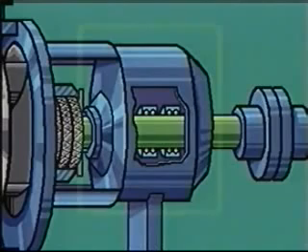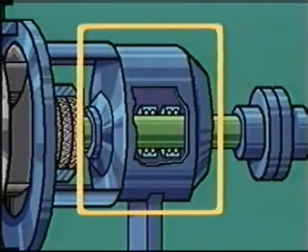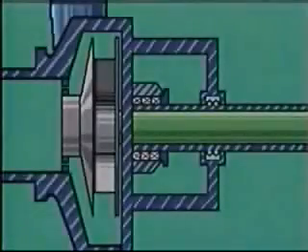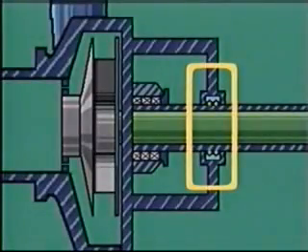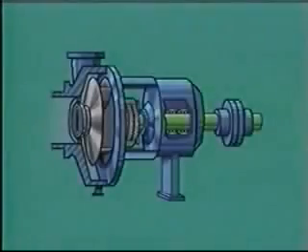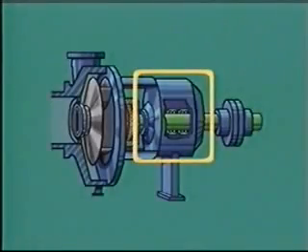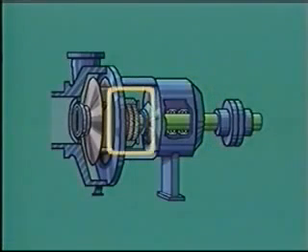Now to bearings. They support the shaft and reduce friction as it rotates in the casing. They do even more. They control the forward and backward movement, the thrust of the shaft, as well as the shaft side-to-side or radial movement. That keeps the shaft from rubbing against the pump casing. Bearings can be here, in the pump casing on small process pumps, or separated in special housings on larger ones. Last, are seals, or packing. They're used to stop or cut fluid leakage around the shaft.